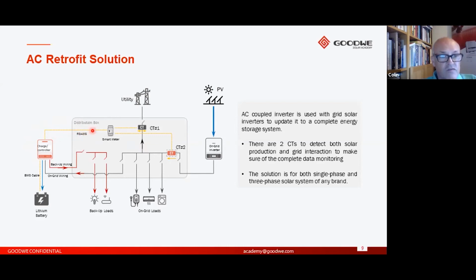A slight difference from when I showed you the charge controller earlier is that the RS485 communication goes to the smart meter here, and on the output side we have a CT exactly the same as before, which performs the monitoring of the incoming and outgoing power to the grid. But we now have this second CT, which is there purely to monitor the power generated by the existing inverter. What that enables is that on our SEMS portal, you can now monitor and show the amount of power being generated by the inverter.